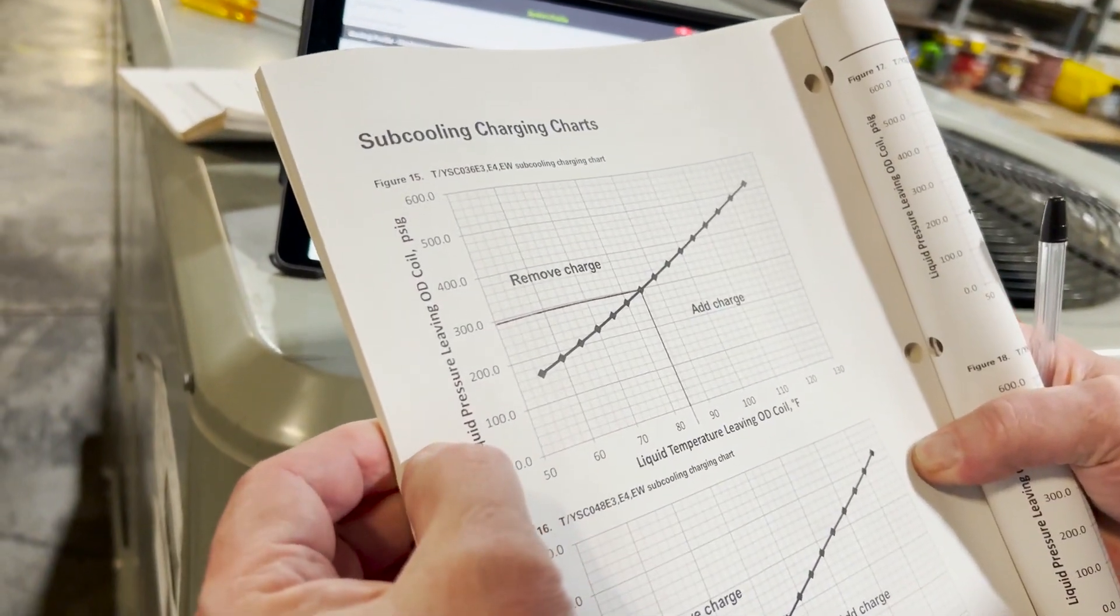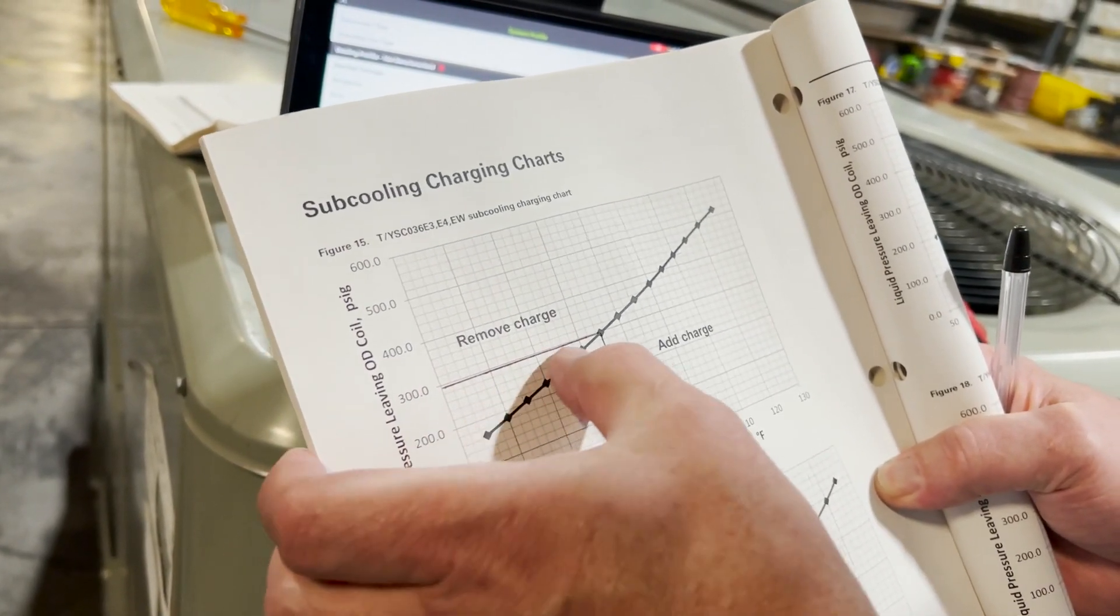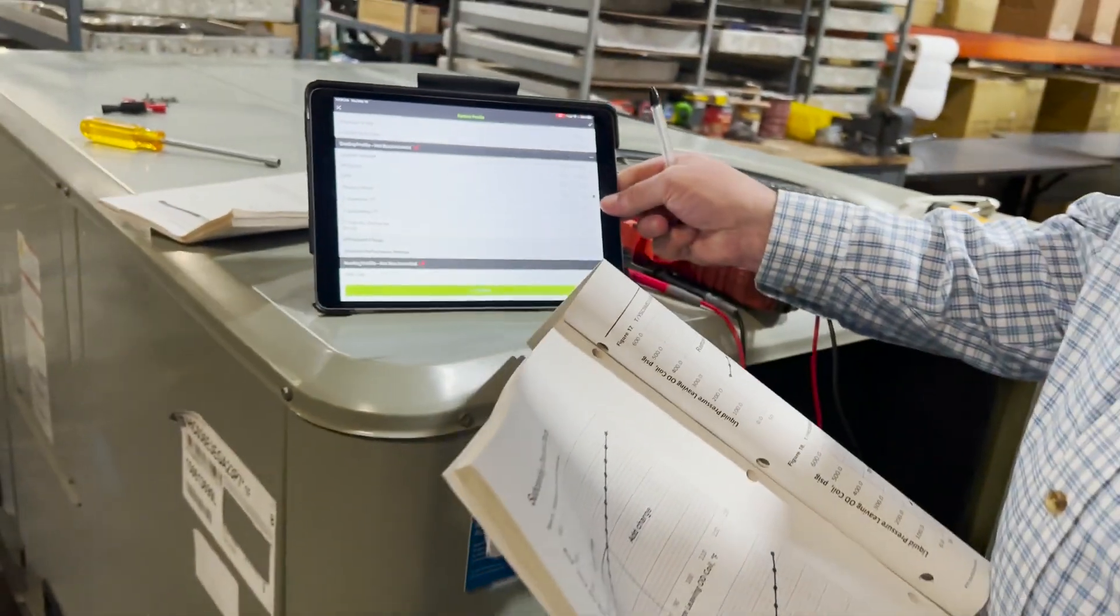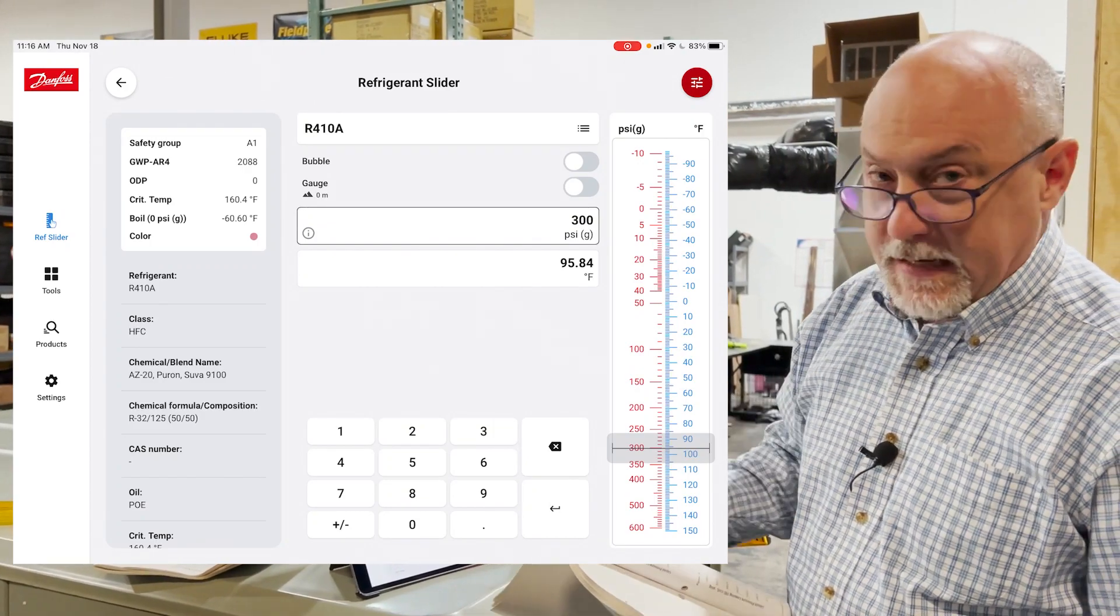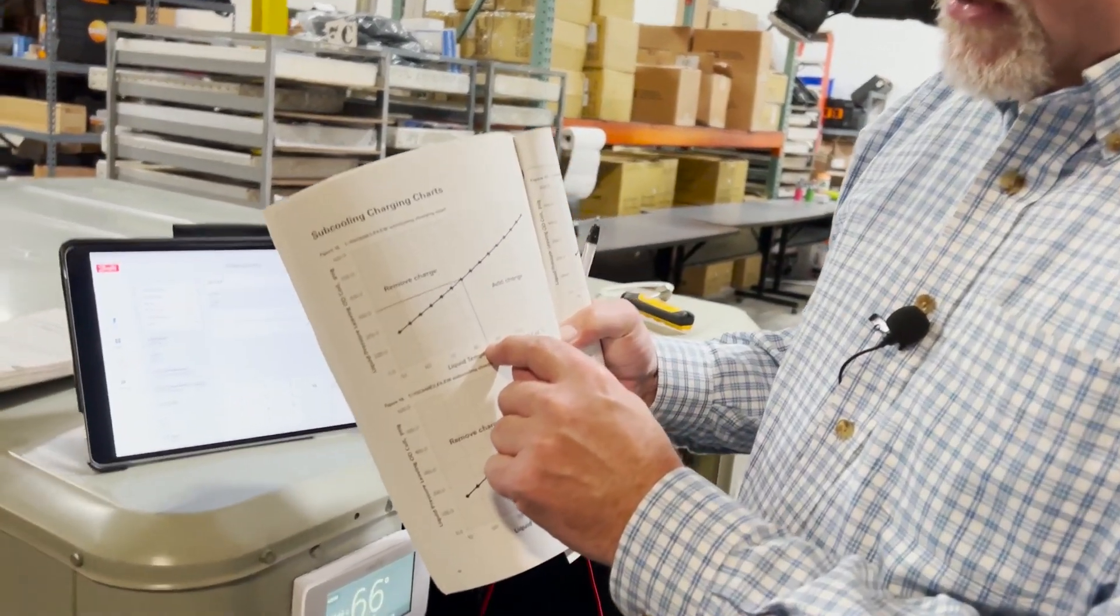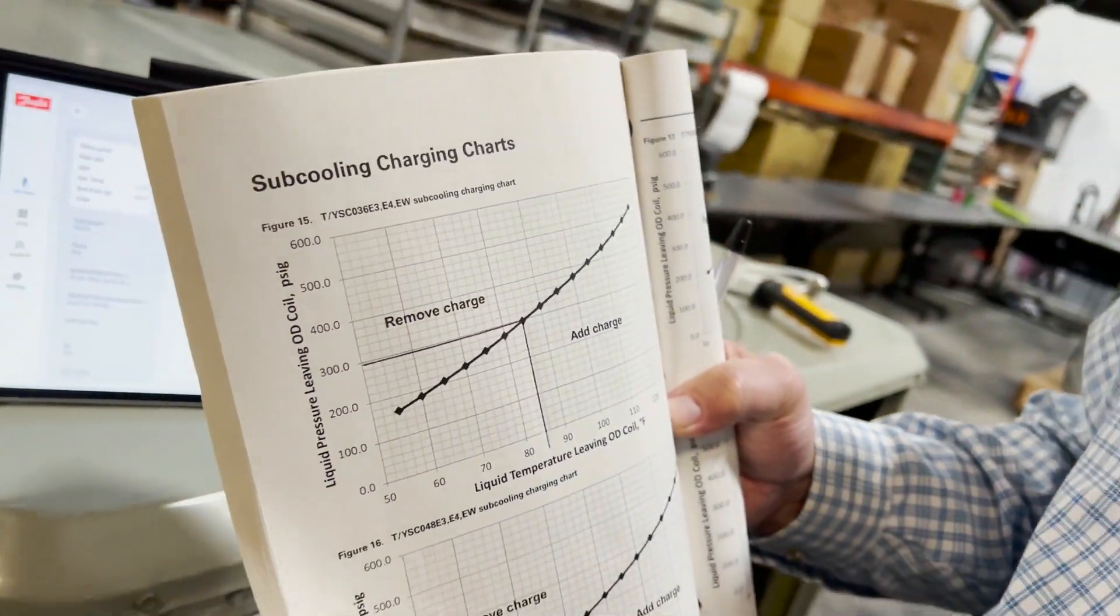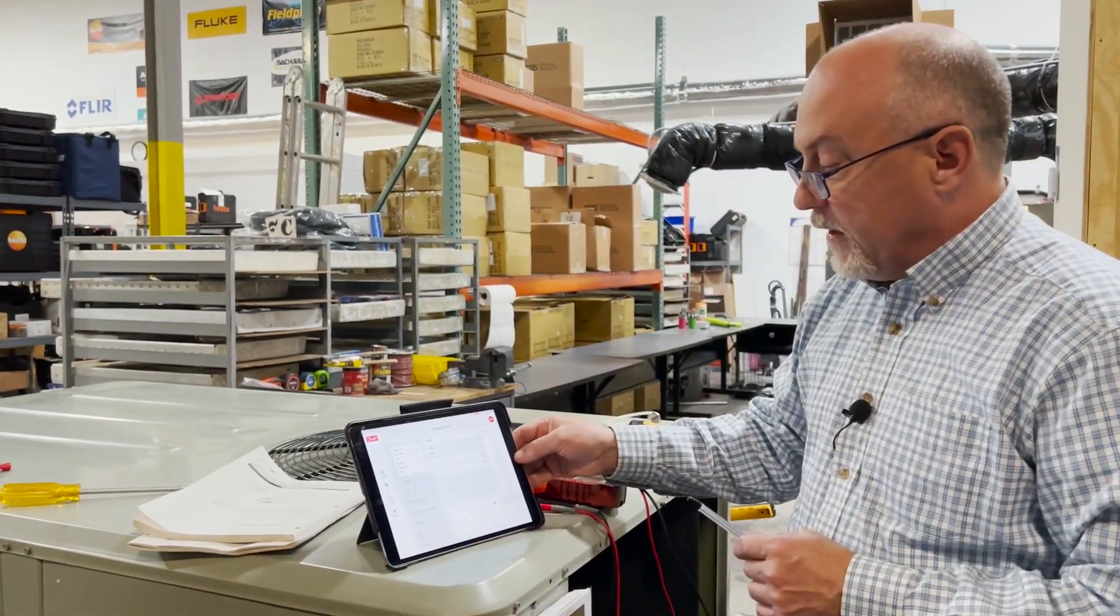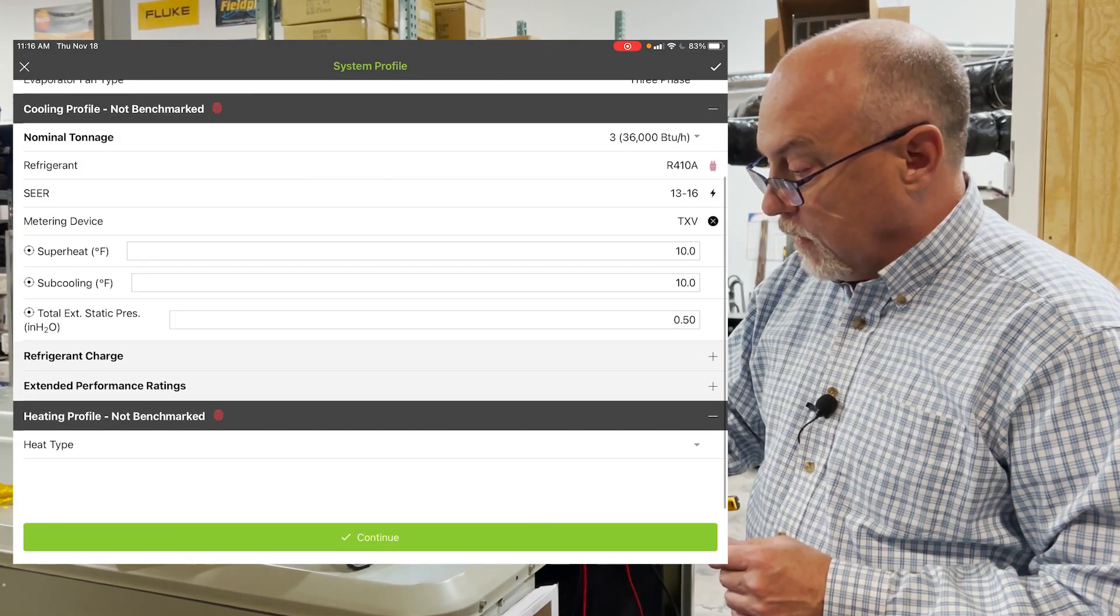Now, Trane or American Standard, if you take a look at this, I'll have Val come over so you guys can see what's going on here. They use a chart where you have the liquid pressure leaving the outdoor coil. So in this case, I just drew a line from 300 over until it crossed and then show the corresponding temperature. Now, if you look at the Danfoss app for a minute, you'll see at 300 PSIG, we're at 95 degrees condensing temp. If you go back to this chart here, you'll see that this correlates to 85 degrees. So 95 minus 85 is 10 degrees of sub-cooling. And so in the MeasureQuick app, that's what we're going to set this thing up for is 10 degrees of sub-cooling in the profile.